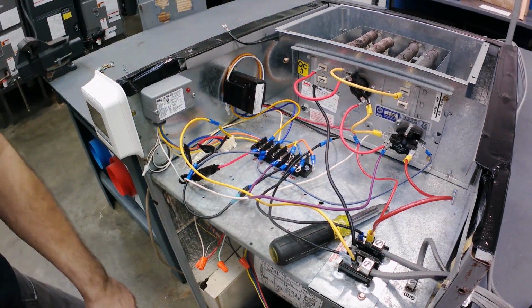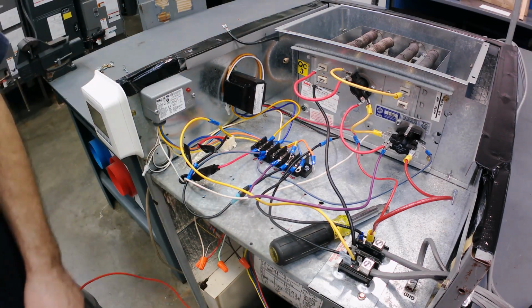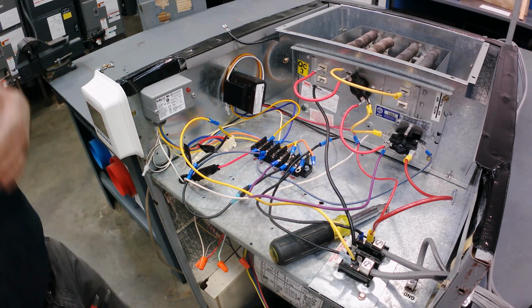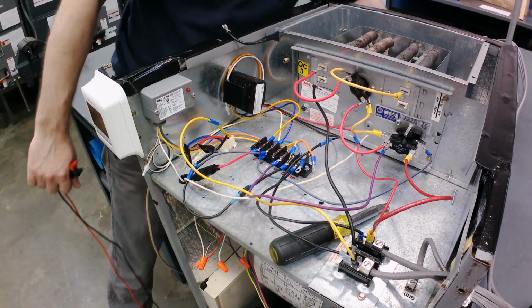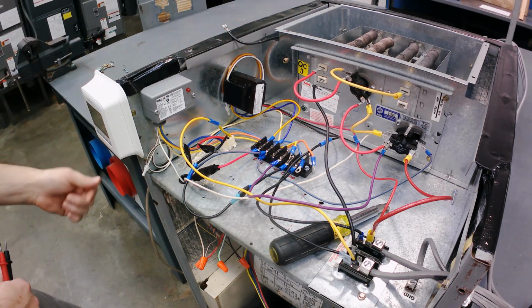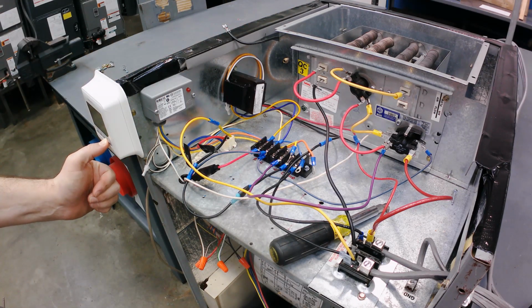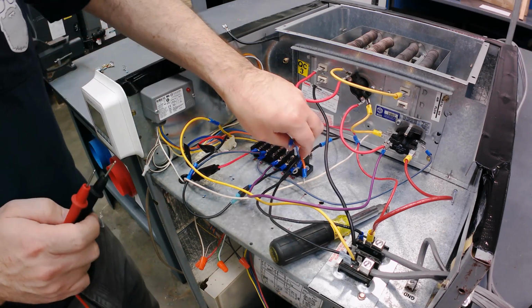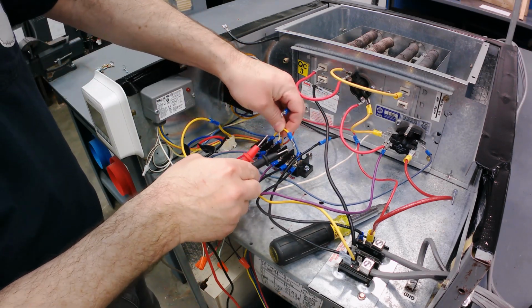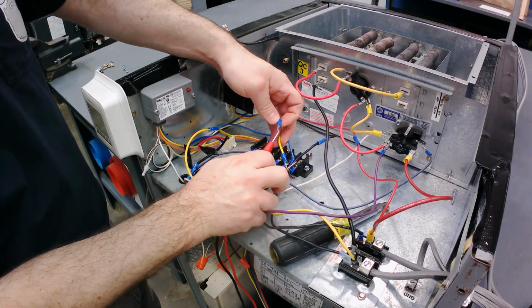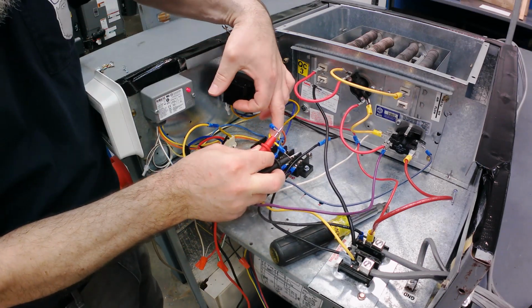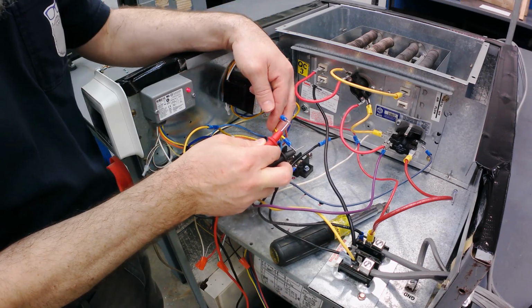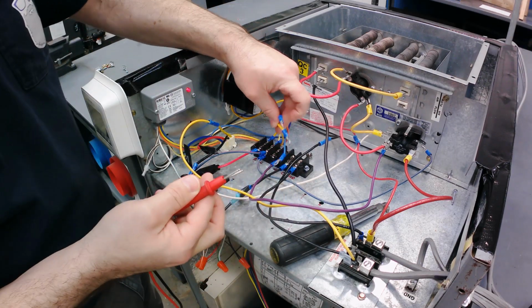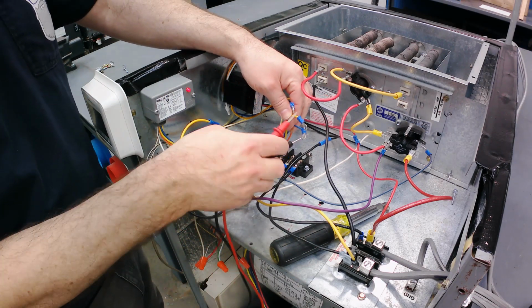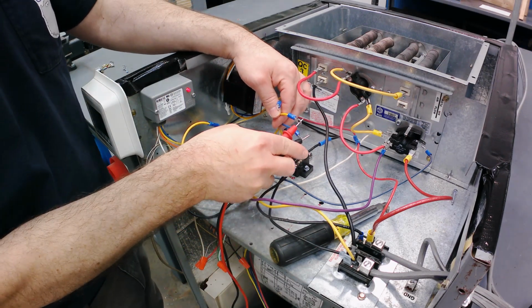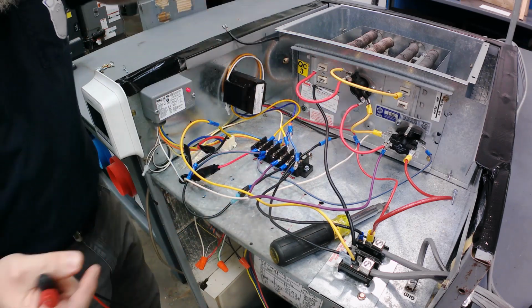I could go back to the breaker and turn it on, and we could watch the switch close. We can watch this switch close whenever that LED light, there we go. So the light came on indicating that the coil had voltage, and our normally open switch closed, and we can double check our normally closed switch, and there's no tone there.